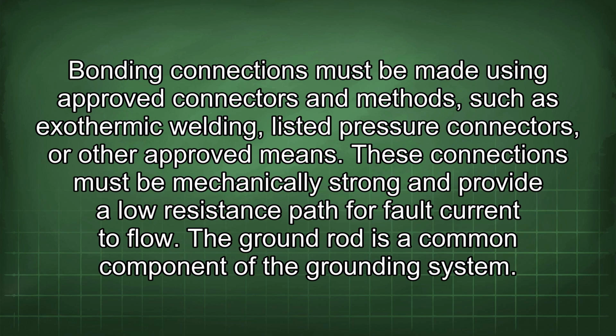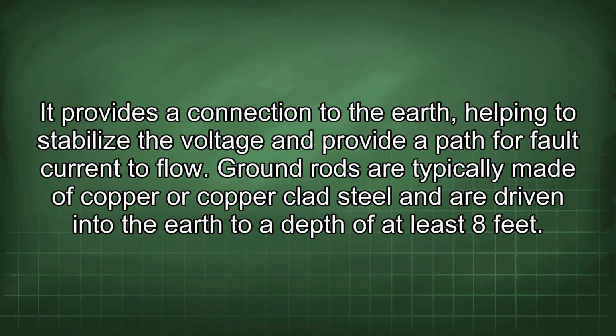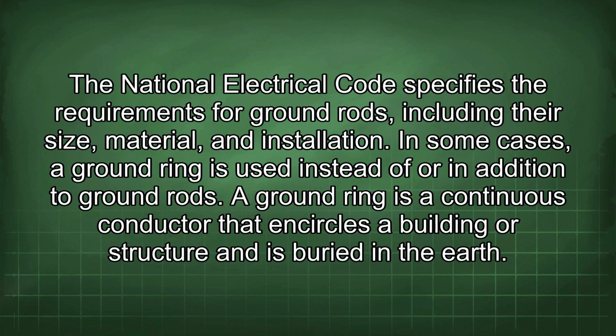The ground rod is a common component of the grounding system. It provides a connection to the earth, helping to stabilize the voltage and provide a path for fault current to flow. Ground rods are typically made of copper or copper-clad steel and are driven into the earth to a depth of at least 8 feet. The National Electrical Code specifies the requirements for ground rods, including their size, material, and installation.